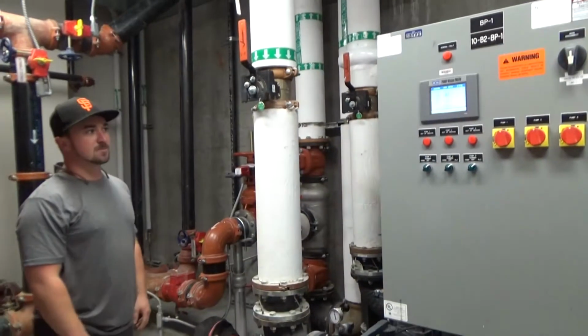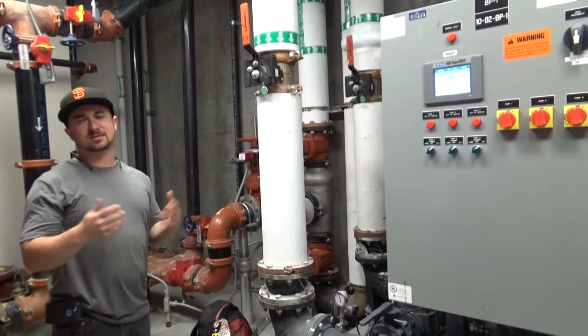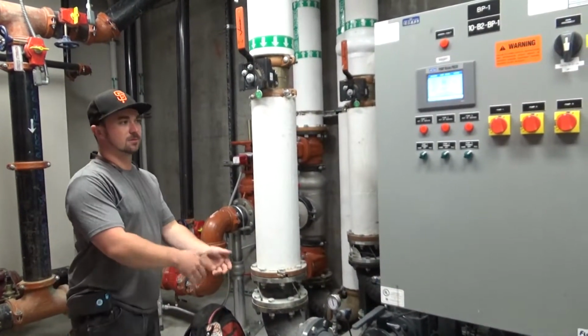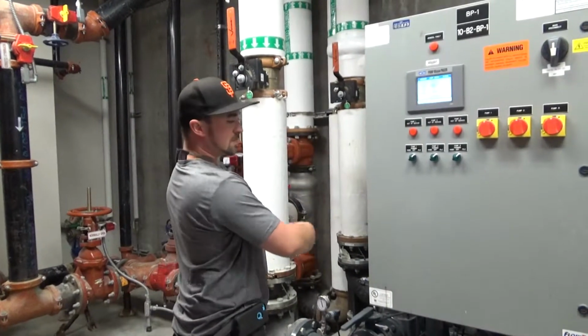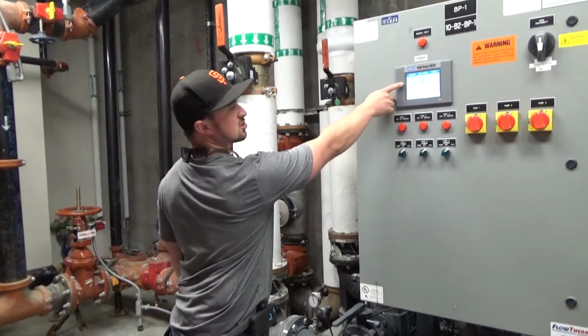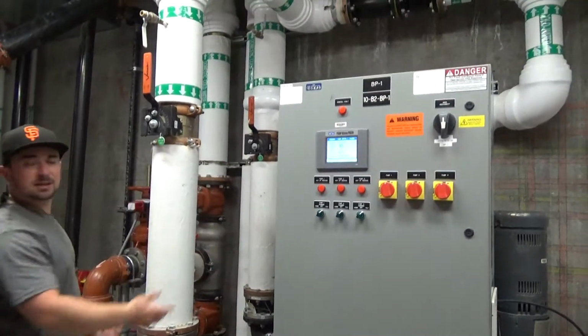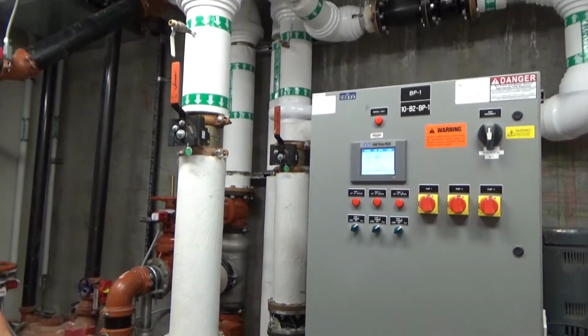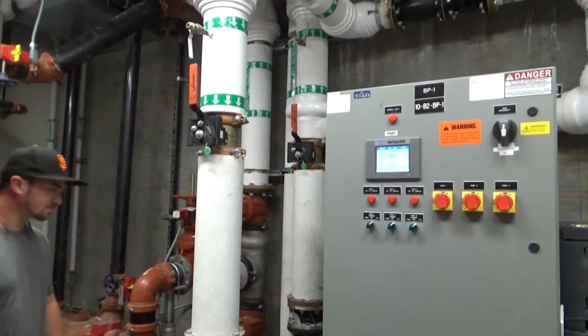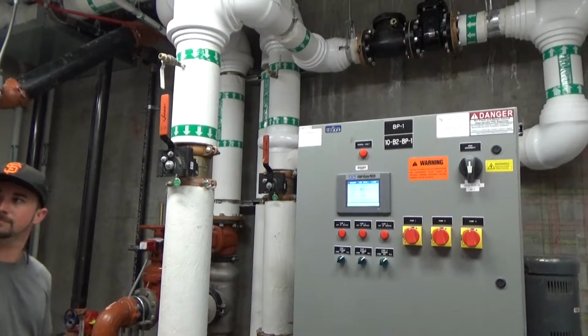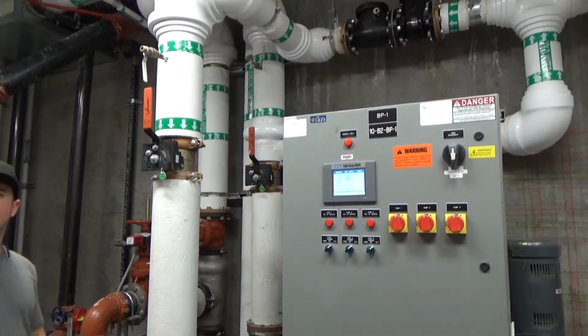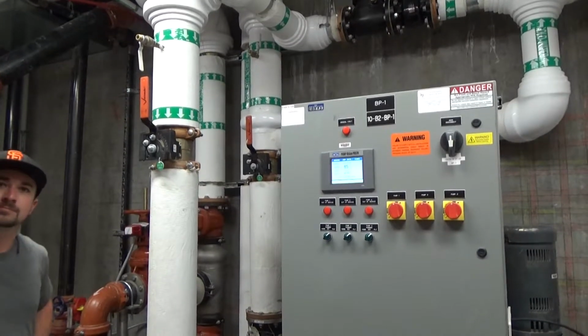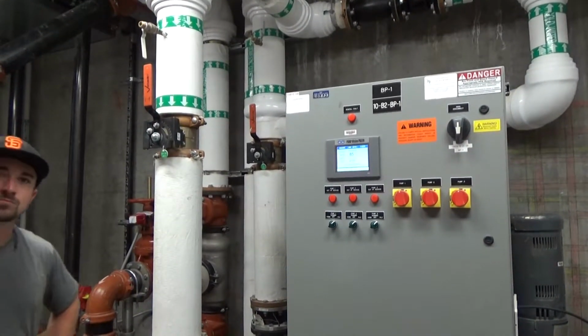Most places have a set point higher than that. They'd say they want 150 as a set point, so then these pumps will be running all the time. But you guys are pretty much just using it as a backup in case city water drops to a lower pressure, which is cool. That's good. And if we lose city water and we go to our reserve, it will probably take it then as well. Yes, exactly. So right now, you tell us what is the pressure on the city water, right?